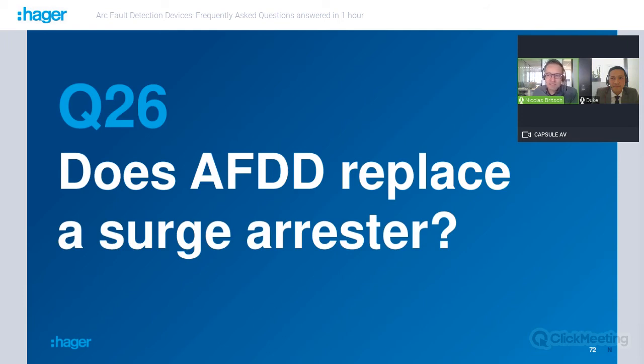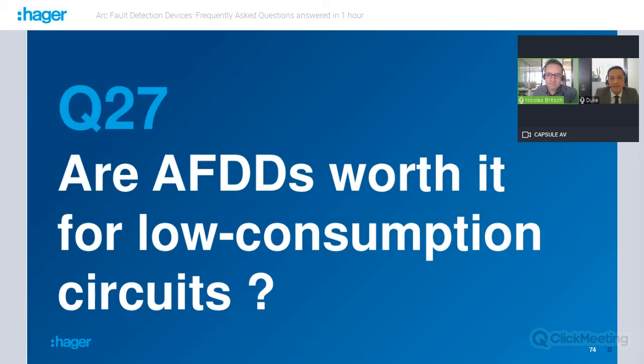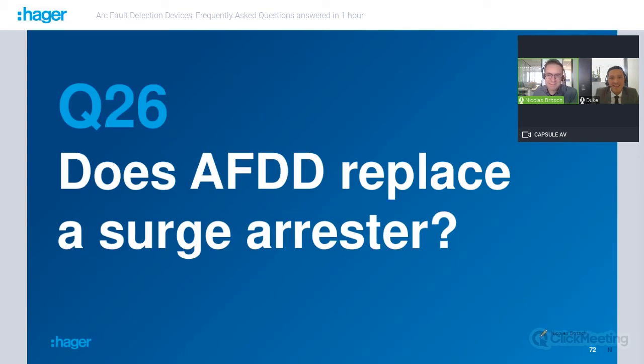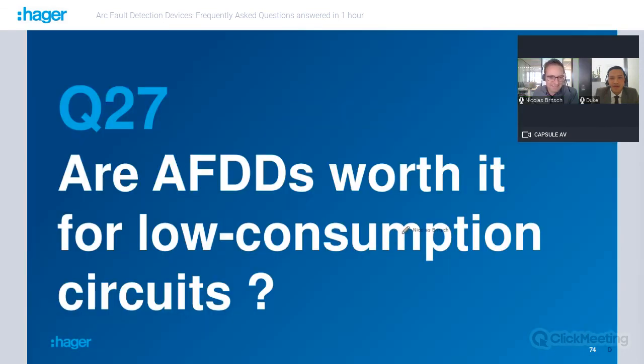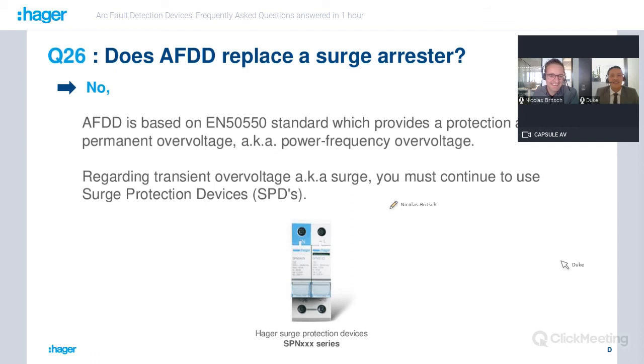But talking about overvoltage and surge, for example, Duke, does an AFDD replace a surge arrestor? So AFDD cannot replace a surge arrestor, but it can protect against overvoltage at power frequency that Nicolas explained. And with AFDD, you still need to use surge protection devices. And we can use our range in Hager. We have this product as well, of course.